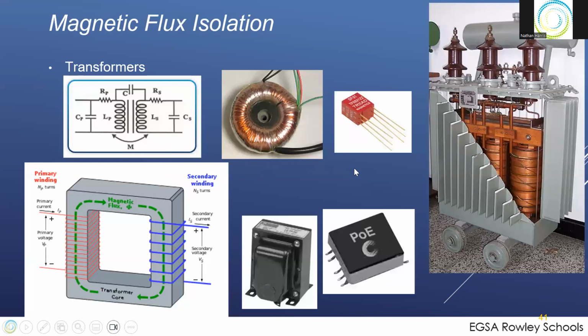Magnetic flux isolation is another one. This is used, obviously quite a bit in AC power circuits, CTs, PTs, things like that. They also have small transformers on circuit boards that are used for isolating signals. Your CTs often come in to a controller, and before they get A to D, analog to digital converted, they're dropped down to a low level through little onboard transformers. So magnetic flux is another force.